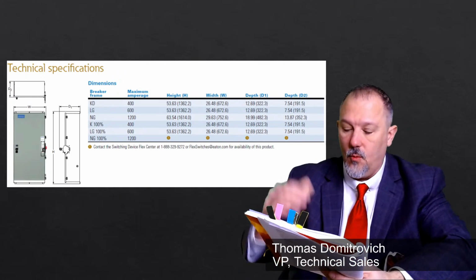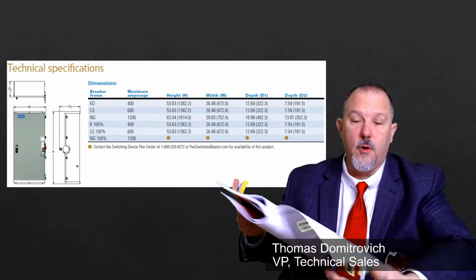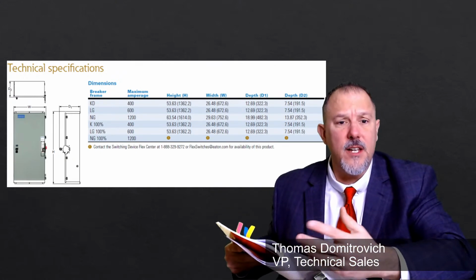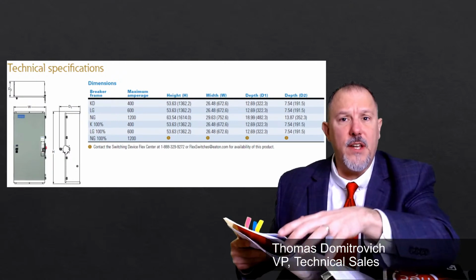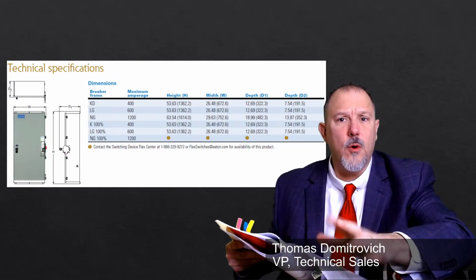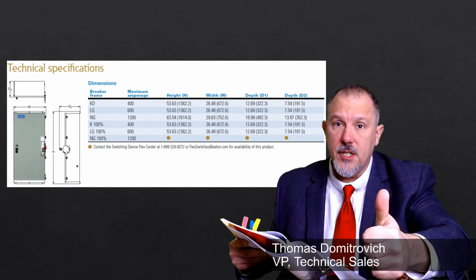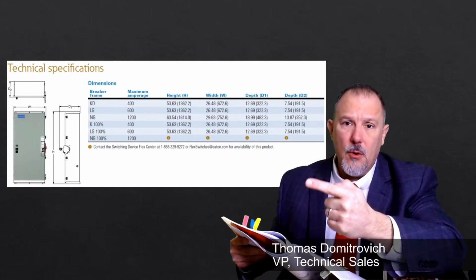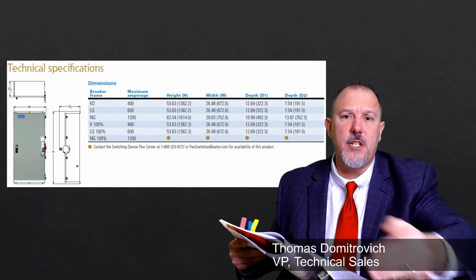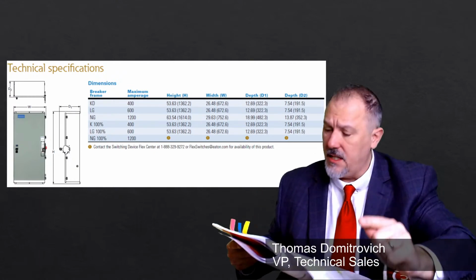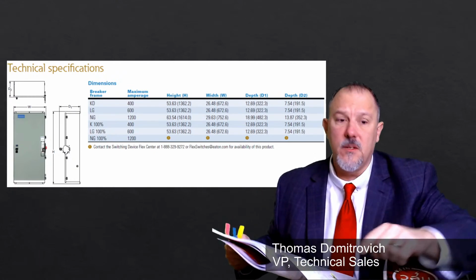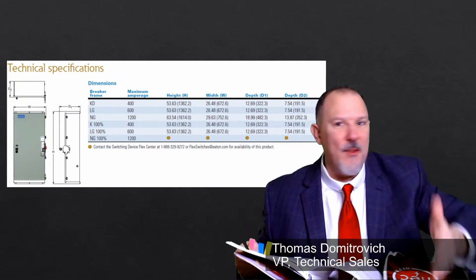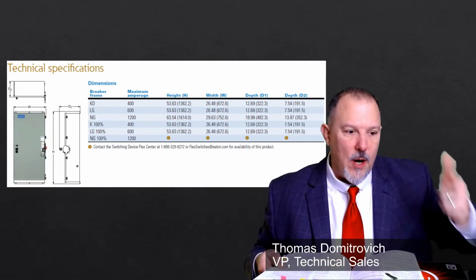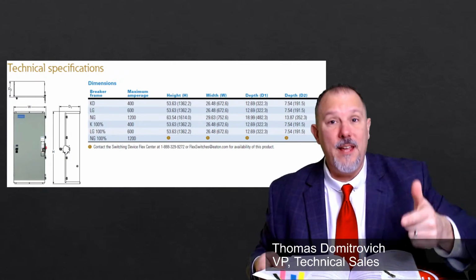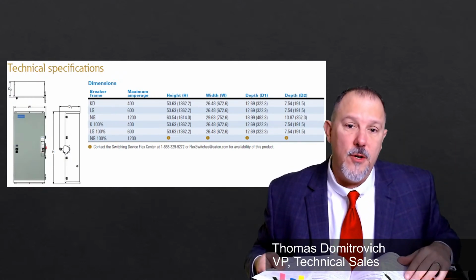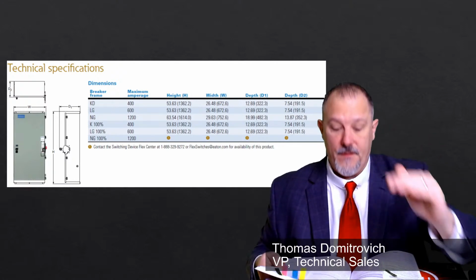Infeasibility is one of the options you consider when performing troubleshooting. That's why in our facilities we put the enclosed circuit breaker in front of equipment where we know justified energized work could occur. We promote establishing the electrically safe work condition: pull the handle, lock and tag it out, go through the procedures in 70E. But when that's impossible, after you've gone through your hot work programs and asked all those questions about why you can't shut this down, put this in arc reduction mode and you will reduce the severity.